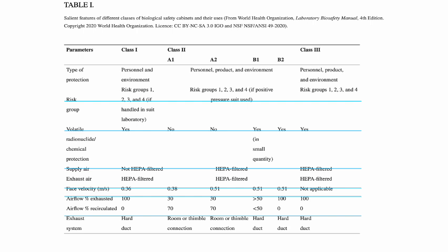Okay? And in terms of the percentage exhausted and recirculated, as you can see here, only class 1, class 2 B2, and 3 are the ones that have no recirculated air. Tandaan nyo, class 1, class 2 B2, and class 3 are the only cabinets that do not recirculate air. For the others, your class 2 A1, A2, and B1, meron po silang percent na nare-recirculate. For class 2 A1 and A2, pareho po yung percentage exhausted nila. It exhausts 30% of the air and it recirculates 70% of the air. While your B1 naman, more than 50% of the air is exhausted and less than 50% is recirculated.